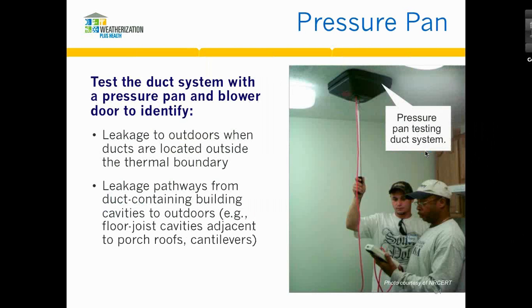And then we test the ducts. Ducts, not talking about mallards, it's a tough word to say, but the duct system delivers our conditioned air where we want it, and they're typically operating at some kind of pressure. So if there's a leak in the duct, we're losing pure conditioned air at pressure. It's far more expensive than a leak, say, around a window. Maybe less noticeable comfort-wise when you're sitting by the window, but definitely more noticeable on your energy bills and the overall performance of the house. So we test the ducts to find out how leaky they are.